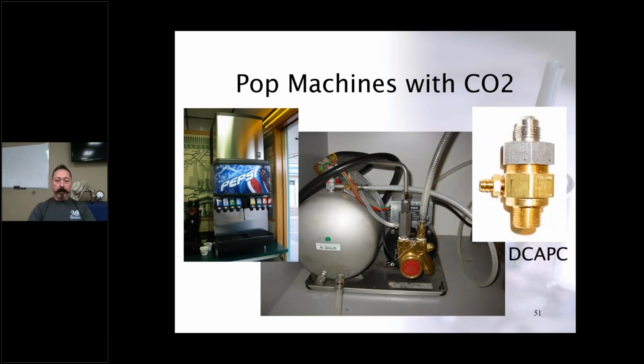Pop machines. There's something called a post-mix beverage machine where it mixes your CO2, your water, and your syrup. And here we've got the mixing valve in the middle that mixes all those things to make a pop. But the CO2 is under a lot of back pressure, and if the regulators on that system malfunction, it'll back pressure CO2 into the potable drinking water supply.